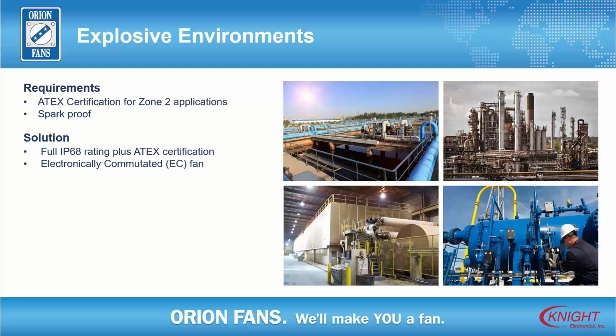And if you have a gas leak or a dust environment or what have you, Zone 2 is not made to be in there all the time. It's not made to be like in a gas chamber all the time. But it could have gas leak into it, like at an oil field application where you might have a short-term gas leak or what have you. They're made for that. That's what the Zone 2 does. Anything that's got a lot of very, very fine dust particles is what requires the ATEX.